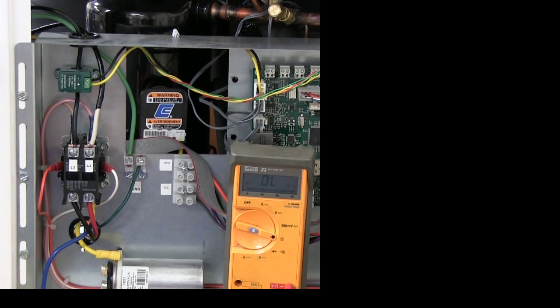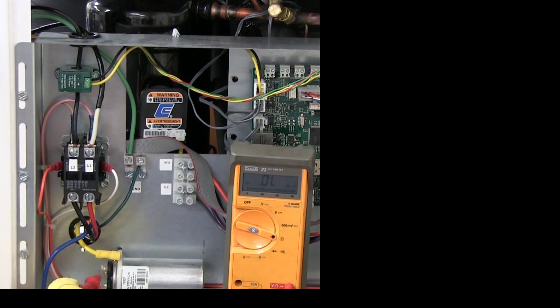Since I've done that, I can continue on to test the run capacitor. The very first step would be to make sure that the capacitor is discharged. Whenever these two leads are connected to the capacitor, it will automatically discharge the capacitor through the compressor windings. I've already disconnected them, and I will do a test.